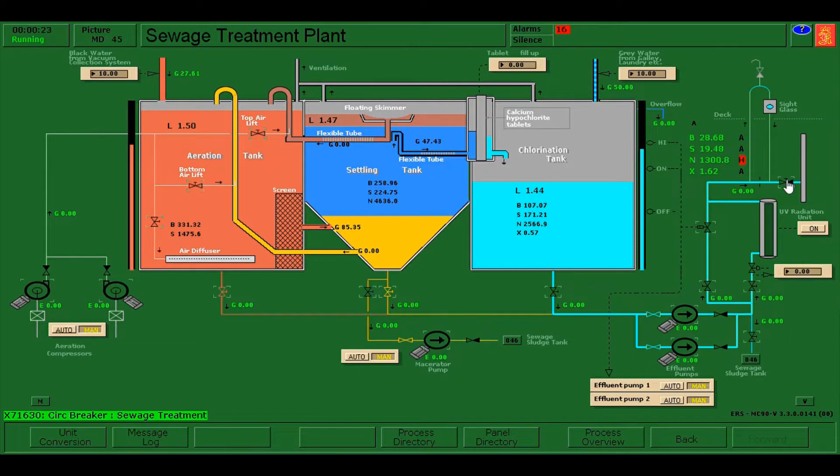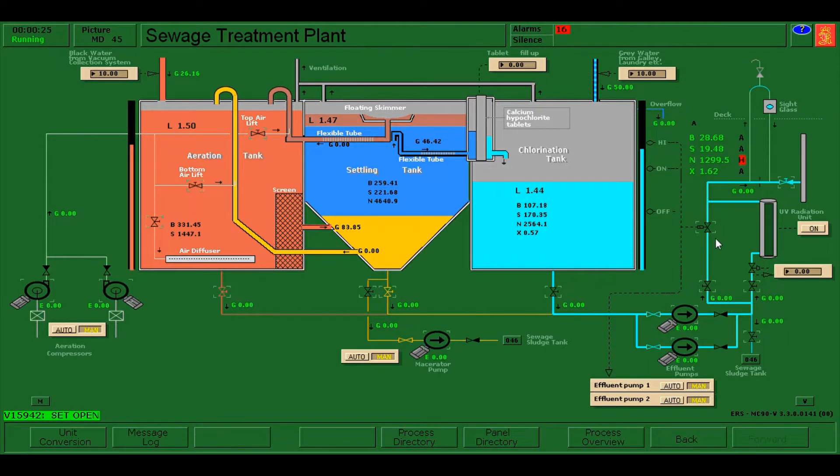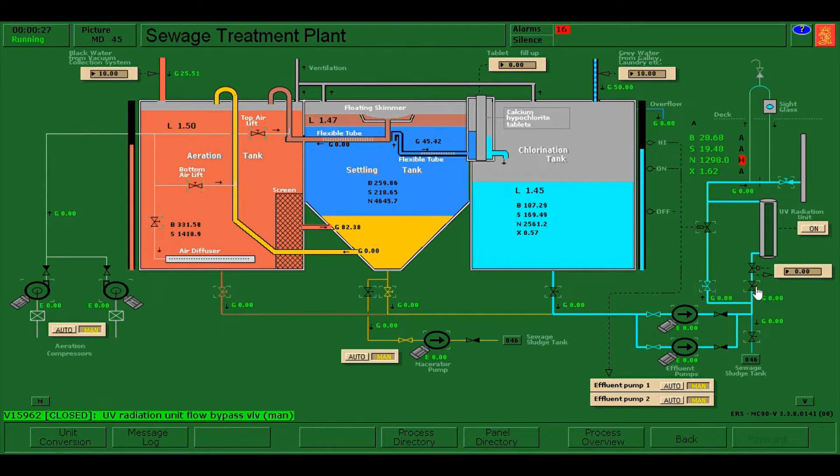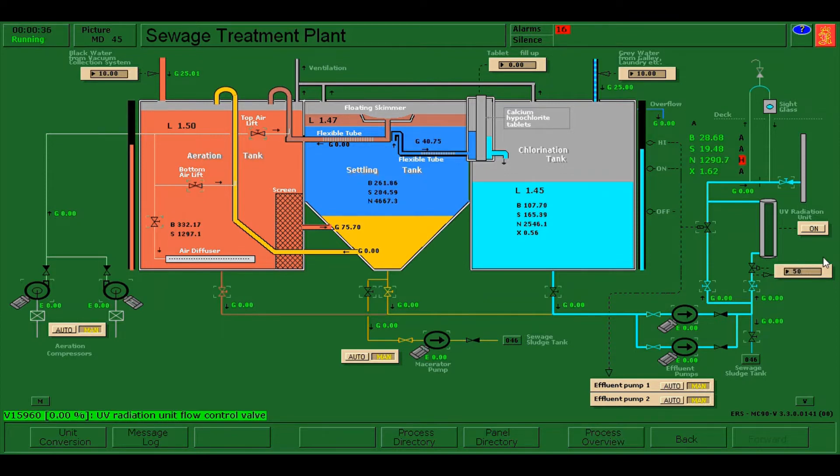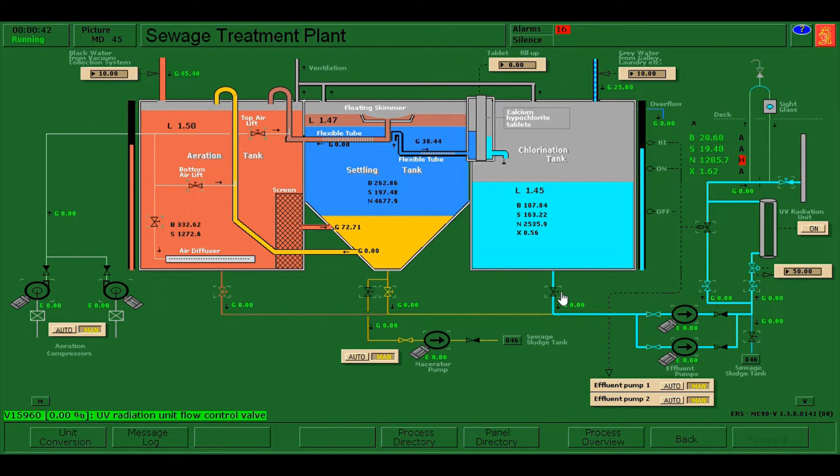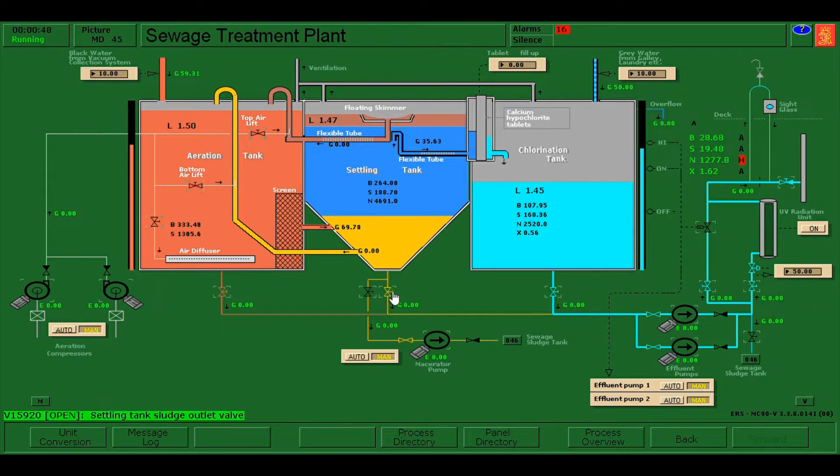Then I'll open the discharge valves on the discharge line from the pump. This valve should be 50% open, going to the UV radiation unit, and I need to open also the chlorination tank discharge valve.